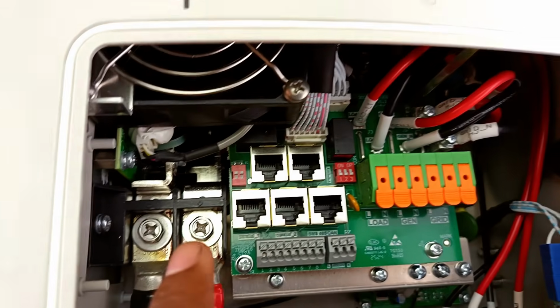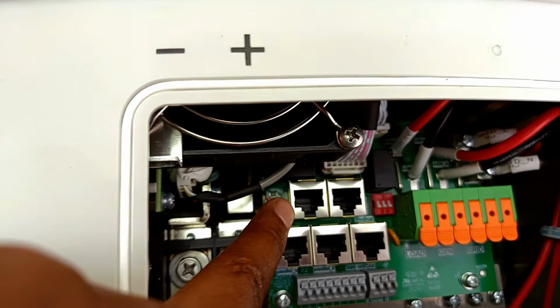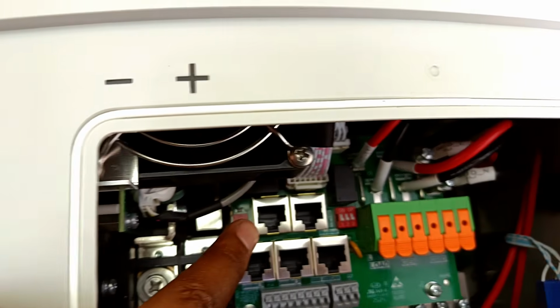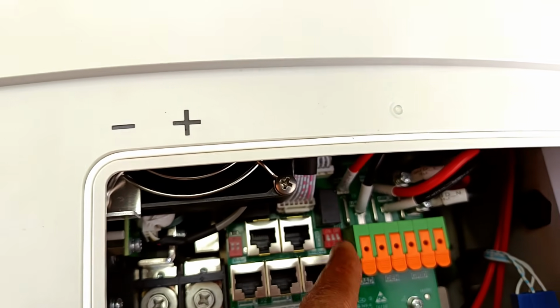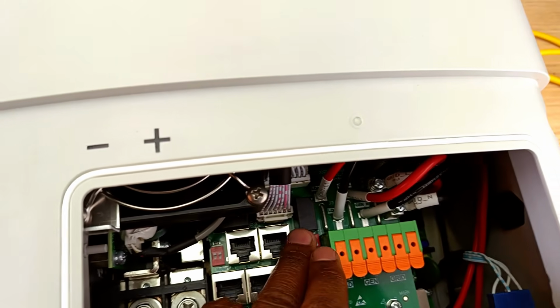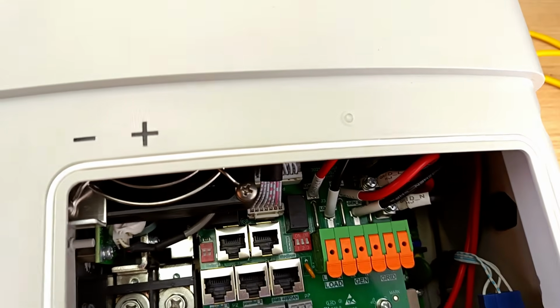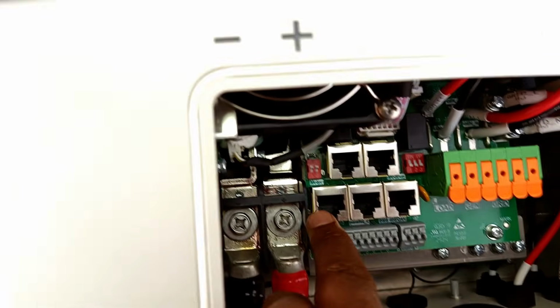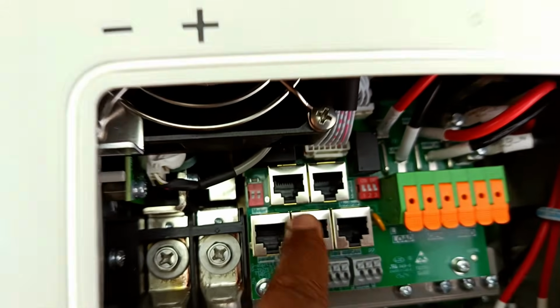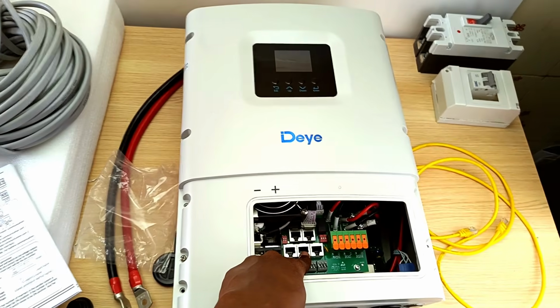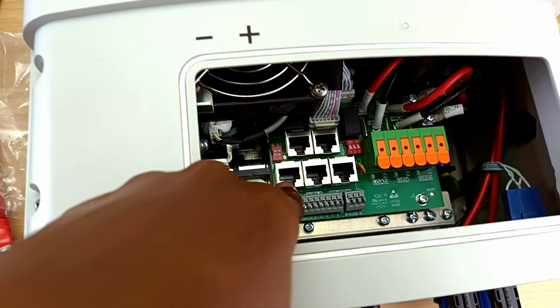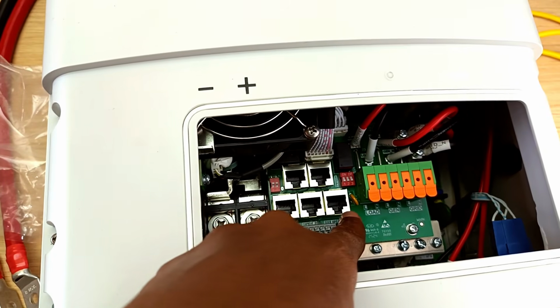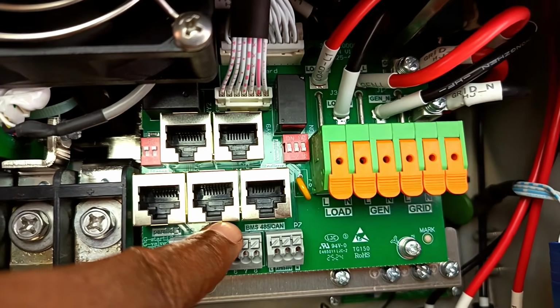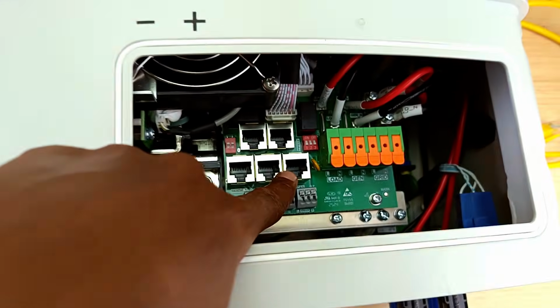Now, let's talk about the communication ports. The first one here, that's for energy meter communication. The second one is Modbus, that is reserved. For most applications, you will never use this. Now, these two ports are for parallel communication ports. They are also labeled there. If you connect this inverter in parallel with other inverters of the same model, you are going to connect these inverters together using these two ports. And the most important one that I will also use is this one here, labeled as BMS CAN. Now, this is for battery communication.